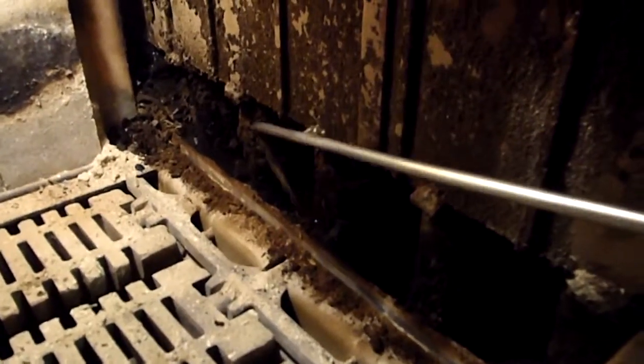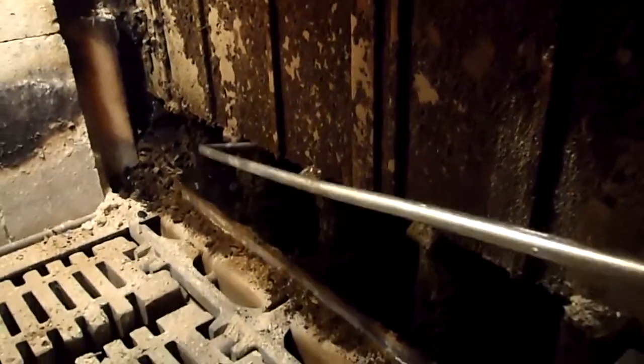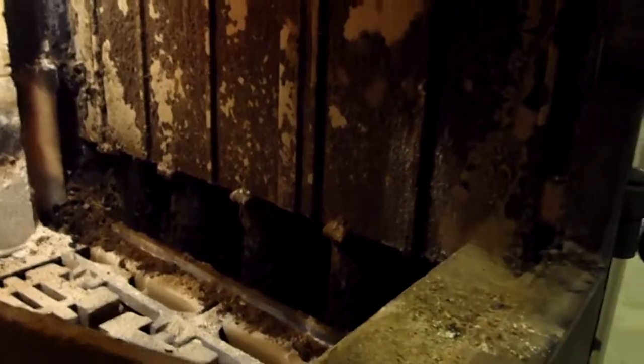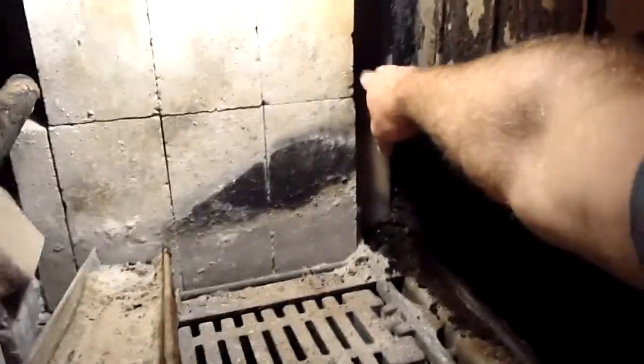So this all has to be removed for safety purposes. All this on the tubes will have to be removed. If the brush is off for the most part, it just has to be removed. And this plate comes out. There's a bolt right there. I noticed some of the new ones now, they're actually putting a spacer on that bolt and bringing it out so you can actually get to it and not have any issues. So that's basically how you take that one wall out. And again, I forgot that little sliver.